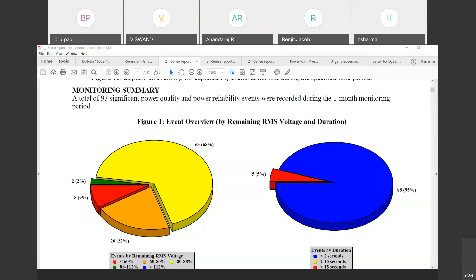Yes, sir. When we look at the data on the voltage sags, I can even take you straight to those situations. I hope you can see my screen now. This is the kind of disturbances that they were facing. If you look at the overall nature, voltage sags are heavily dominating in these situations. And if at all there is a voltage spike, it is within 100 to 110%. Almost all equipment, including ours, can tolerate such spikes up to a certain percentage. The spikes are not corrected, but a system with spike arresters is capable of sustaining them. But when there is a voltage sag, the system cannot sustain. That is when the sag correction feature comes into the picture. I hope I have answered you, sir.